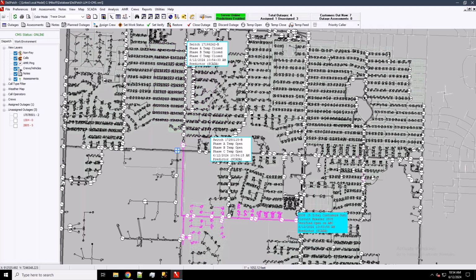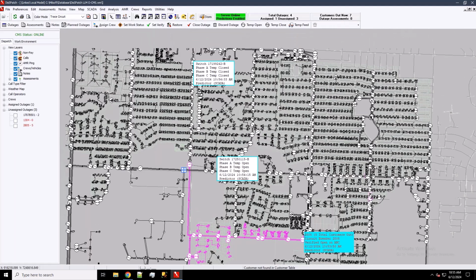There it is. We've temporarily closed the switch on the north side, so that outage now is only affecting 5 customers, 5 active service locations out of power. This automatically restored this entire neighborhood from the north side, backfeeding that circuit.